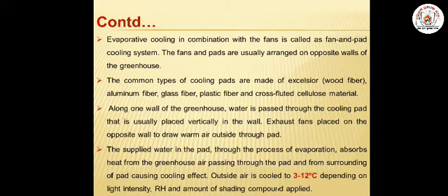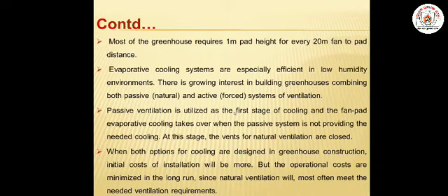Outside air is cooled to the tune of 3 to 12 degrees centigrade, depending upon light intensity, relative humidity, and amount of shading compound which is applied. In this way, the desired cooling effect is obtained inside the greenhouse structure.